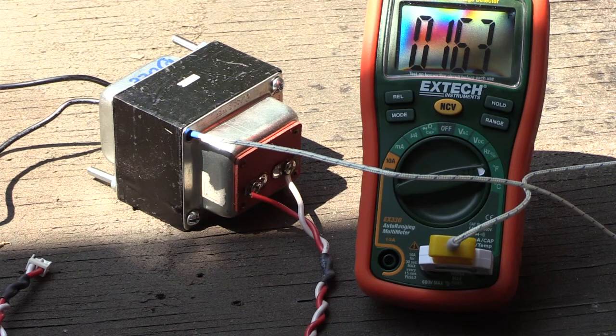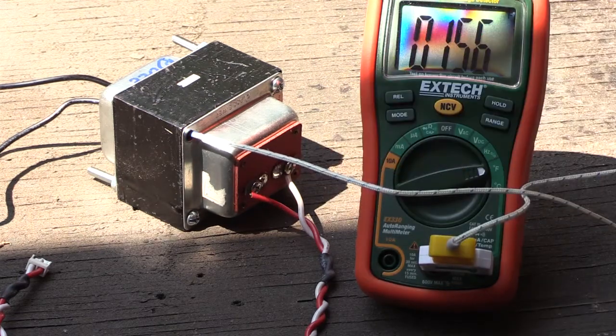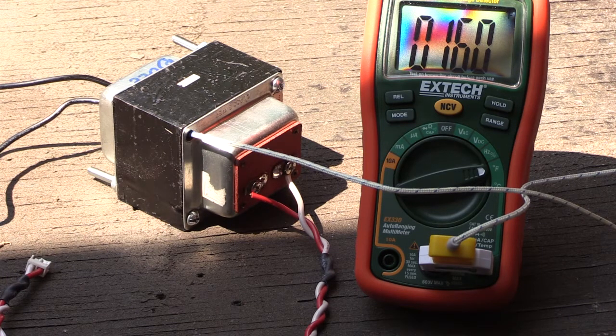So let's review what we've got here. The transformer is still powered up. I took my multimeter with a thermal probe inserted inside one of the rivet holes, so it's reading the internal temperature of the transformer, which is now at 158, 159 degrees. It'll go back up to around 165 if we leave it long enough. The point of this was to show you what could happen if you modify the transformer and take the fuse out.